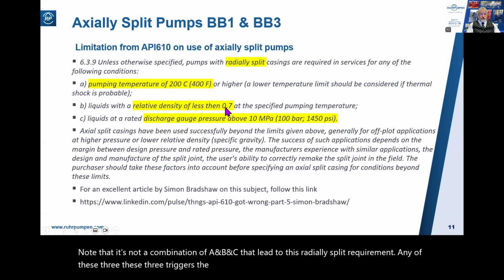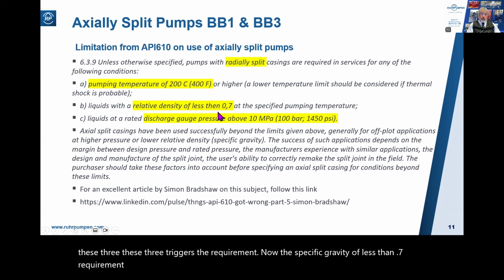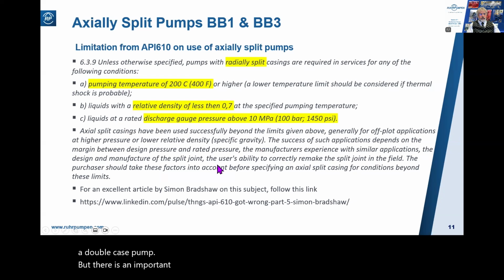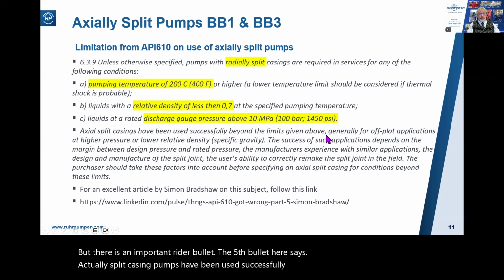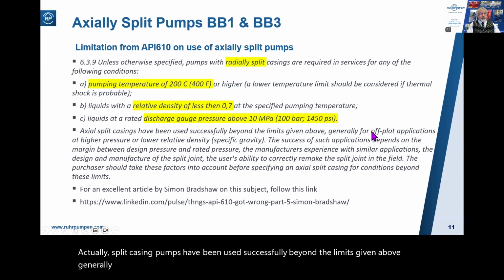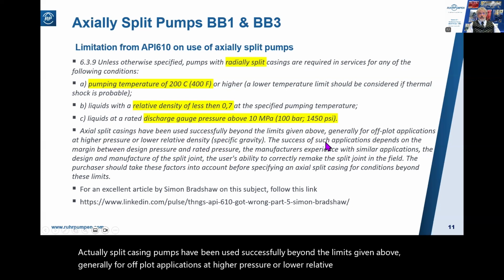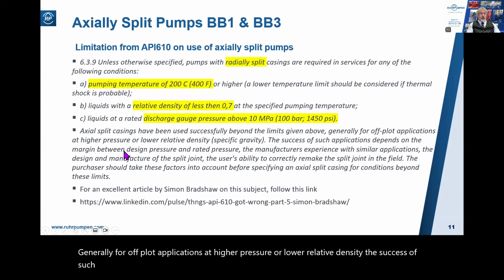Now, the specific gravity of less than 0.7 requirement means any ethane, propane, or butane pump at high pressure would need to be a double case pump. But there is an important rider. The fifth bullet here says, axially split casing pumps have been used successfully beyond the limits given above, generally for off-plot applications at higher pressure or lower relative density.